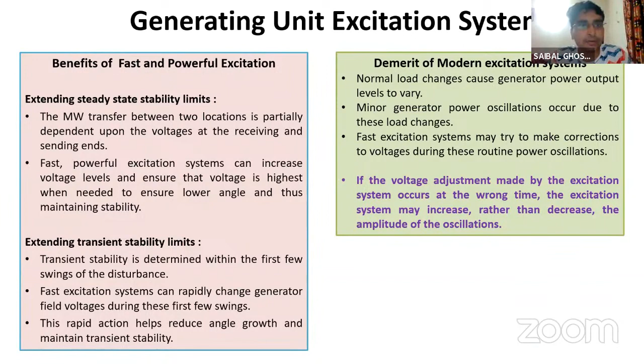I'm skipping all this because I think we are running out of time, and we have mostly explained how PSS works in the initial slide. With constant excitation, you are in the positive direction of synchronizing torque as well as damping torque. But when you add some fast component, the resultant may come into the negative side of the damping torque. Again, if you provide some supplementary control like PSS, it brings the damping torque back into the positive side. Now, why do we need a fast AVR?